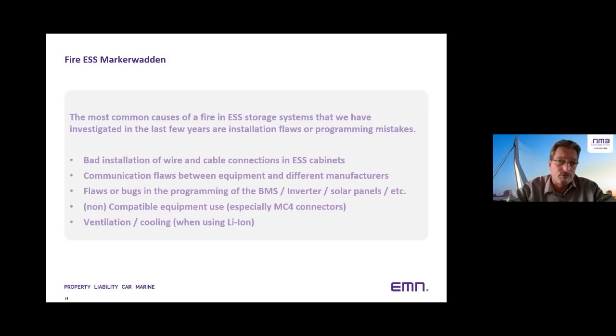For us, the most common causes are installation-related, not the batteries themselves. The batteries are usually ignited by external causes - bad installation, bad programming, or a flaw in programming. That's finally a conclusion of the safety issues we've seen that could be prevented by law or regulation, not only for the battery makers but also for the installers.